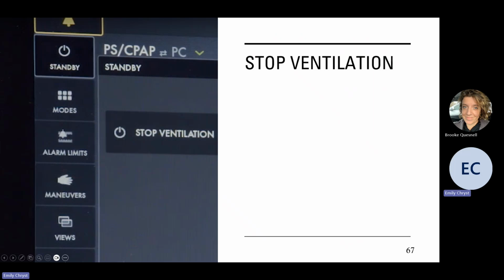All right, and then we have stopping ventilation. So how do we stop ventilation? Whether we're moving a patient or they're transitioning off the ventilator, we need to make sure we're stopping the ventilation in the right way. So you're gonna hit this standby button to force the machine into standby, but you're also gonna have to press and hold that stop ventilation button for 2 seconds. So that's an important one that it doesn't necessarily tell you on this screen.